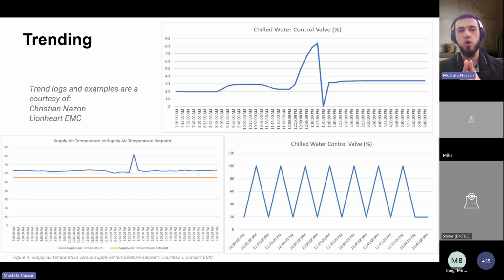Right, now a word of caution to those using older sequence of operations: ensure your climate zone aligns with the economizer strategy. In economizer control, there are various strategies deployed by designers depending on the local climate. ASHRAE 90.1 sheds light on the different control types, like fixed dry bulb, differential dry bulb, fixed enthalpy, etc. For this case, the dry bulb economizer control sequence is enabled at an outside air temperature of 55 degrees, disabled at 70 degrees, and only at points in time in which the outside air temperature is below the return air temperature.